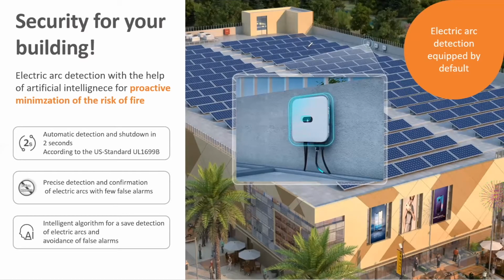Since safety is a big concern in the PV industry, our inverters are also capable of detecting electric arc faults on the DC side. As you can imagine, these are very dangerous because they can cause fires. Huawei's method of detecting these electric arc faults is by using artificial intelligence. And in case something is wrong and you have an arc on the DC side, which is not self-extinguishing, the inverter can detect it, and in less than 2 seconds, it will turn off the inverter, thus preventing any risk of fire.